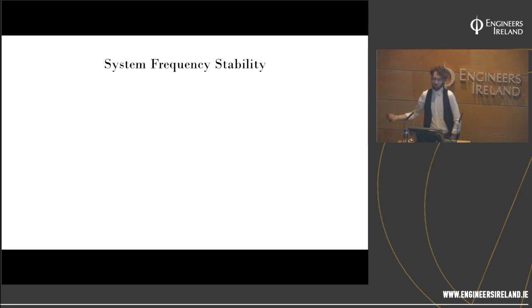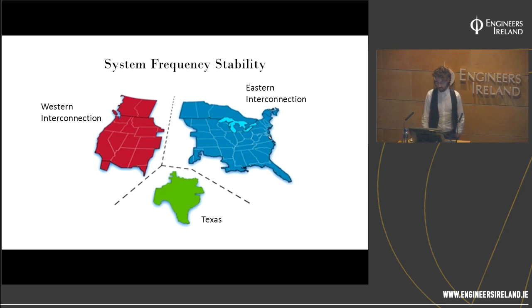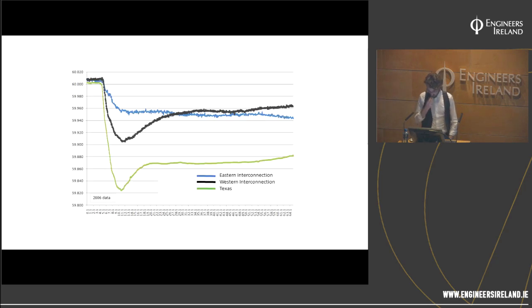But why do we care? What's it all about? As an example, I'm going to take the US power systems. There are three: the Western interconnection, Texas on its own, and then the Eastern interconnection. You can see that Eastern is bigger than Western, and Western is much bigger than Texas. They have different loads, so they're going to have a different number of generators online to meet that load. So the Eastern interconnection has greater inertia than the Western, which has greater inertia than Texas.